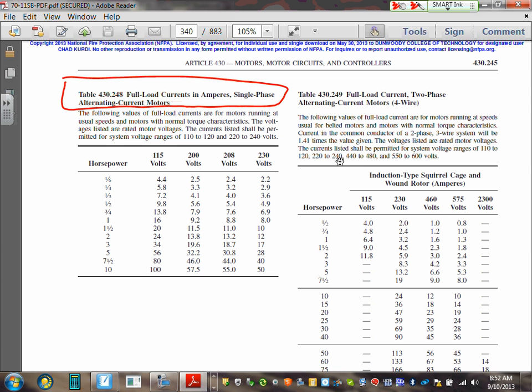The Smarter Than Chad decided, what if we list all the commonly used motors in one table, and we list the full load current for them, so people like Chad, when they're designing a system, don't have to struggle with what the heck is the full load current of this motor? Because to find the full load current of a motor, you need to find the efficiency and the power factor of the motor. How do I know the efficiency or the power factor of this motor? I have no idea. So in order to find the full load current, they have tables in the NEC code book.